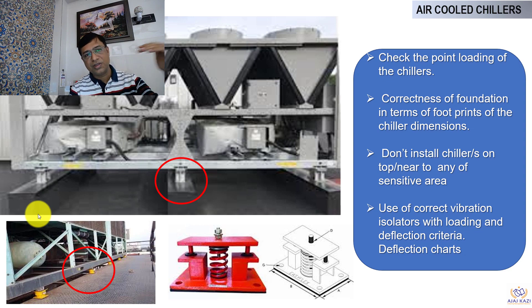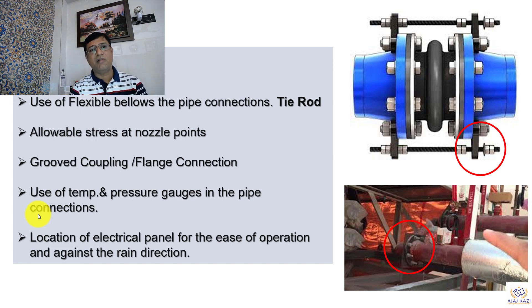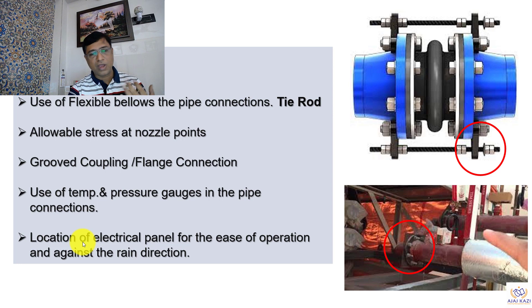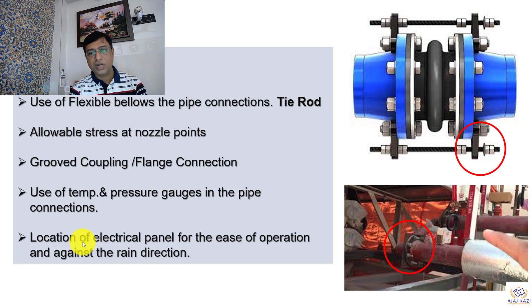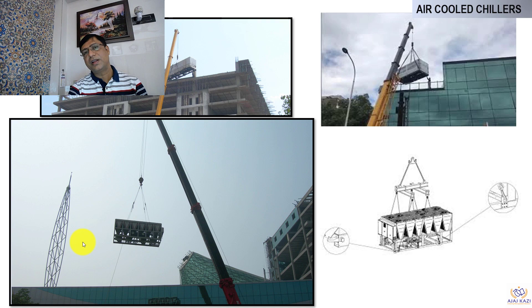We cannot install chillers if there is a sensitive area below without addressing vibration and noise. We also have to check the foundation before installation. When it comes to connections, seismic snubbers are another element that can be added so that in an earthquake event the chillers do not topple. We also have to install vibration bellows — flexible bellows — on the pipe connections to the chillers, as shown here. We can use groove fittings and other elements. The electrical panel should also be positioned considering ease of operation during rain, so that when the panel is opened, rain does not get inside.